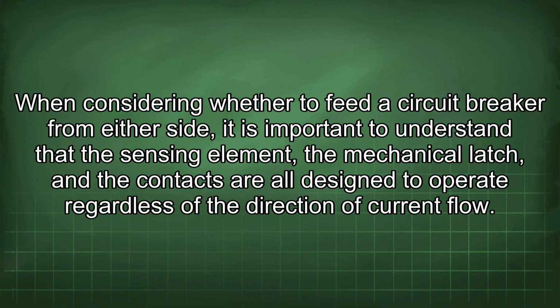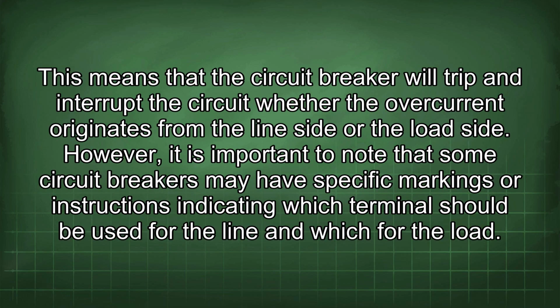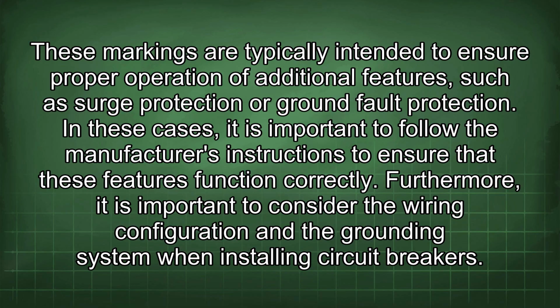When considering whether to feed a circuit breaker from either side, it is important to understand that the sensing element, the mechanical latch, and the contacts are all designed to operate regardless of the direction of current flow. This means that the circuit breaker will trip and interrupt the circuit whether the overcurrent originates from the line side or the load side. However, it is important to note that some circuit breakers may have specific markings or instructions indicating which terminal should be used for the line and which for the load. These markings are typically intended to ensure proper operation of additional features, such as surge protection or ground fault protection. In these cases, it is important to follow the manufacturer's instructions to ensure that these features function correctly.